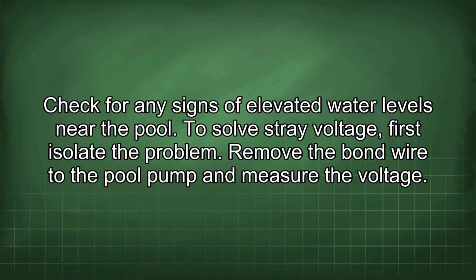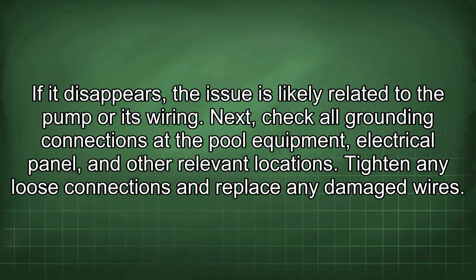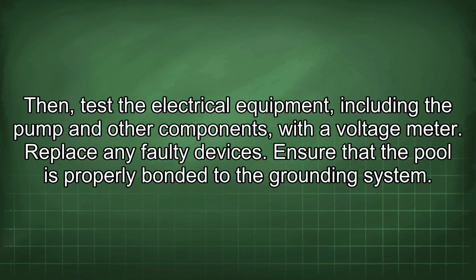To solve stray voltage, first isolate the problem. Remove the bond wire to the pool pump and measure the voltage. If it disappears, the issue is likely related to the pump or its wiring. Next, check all grounding connections at the pool equipment, electrical panel, and other relevant locations. Tighten any loose connections and replace any damaged wires. Then test the electrical equipment, including the pump and other components, with a voltage meter. Replace any faulty devices. Ensure that the pool is properly bonded to the grounding system.